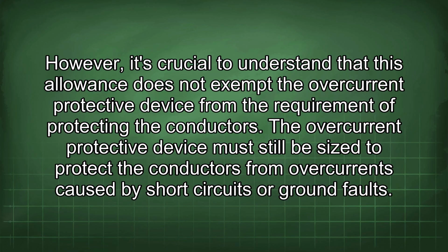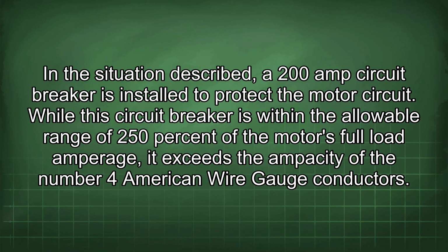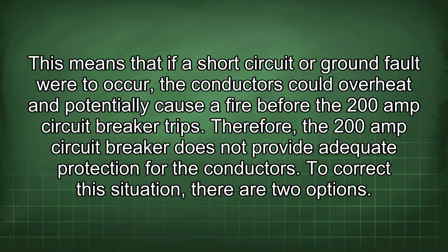In the situation described, a 200 amp circuit breaker is installed to protect the motor circuit. While this circuit breaker is within the allowable range of 250% of the motor's full load amperage, it exceeds the ampacity of the number 4 American wire gauge conductors. This means that if a short circuit or ground fault were to occur, the conductors could overheat and potentially cause a fire before the 200 amp circuit breaker trips. Therefore, the 200 amp circuit breaker does not provide adequate protection for the conductors.